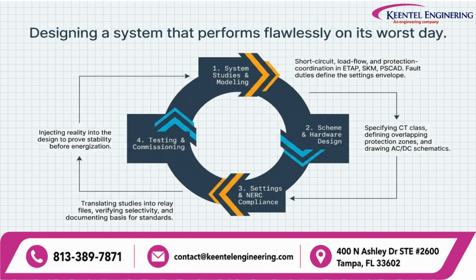The third stage is settings and NERC compliance. Study results must be translated into actual relay settings and configuration files. Engineers then verify selectivity and document the technical basis for the protection settings. And finally comes testing and commissioning.